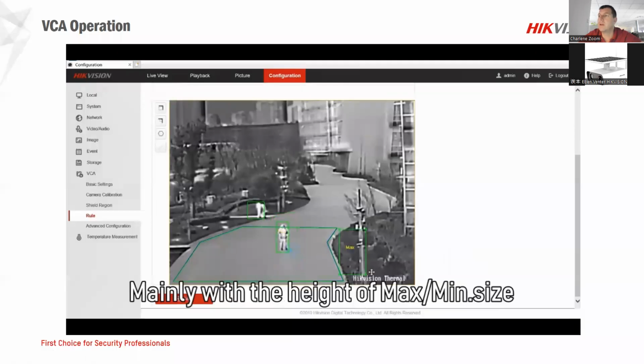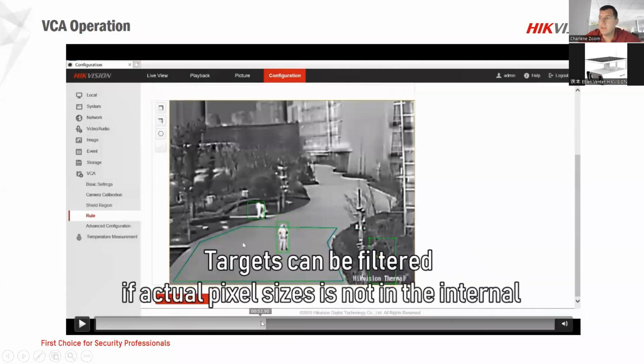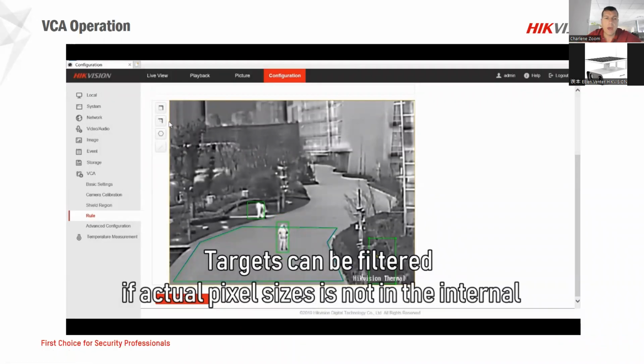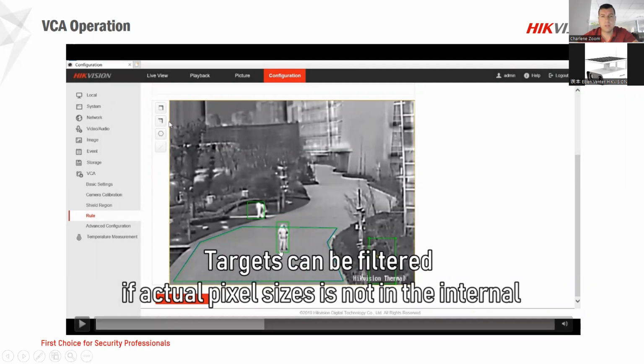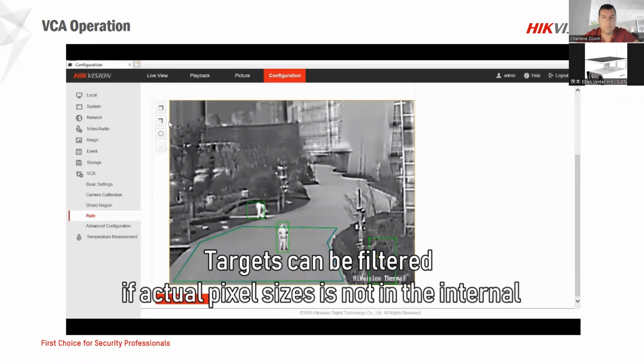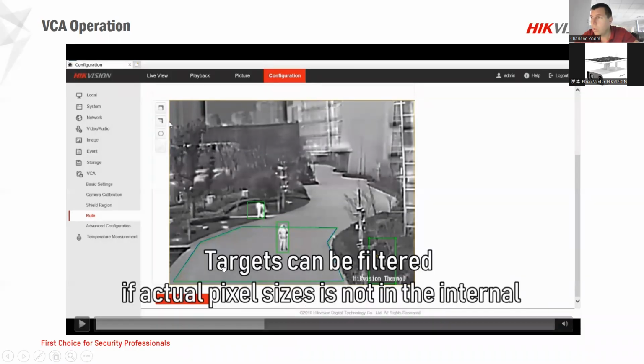So this tool is very nice. And that is another thing to mention. When it comes to this type of setup, with the majority of thermography type of things and any thermo cameras, the best is to do the calibration, and if you want to call it calibration, is to set it up. Right, you need to have that person straight in line of that view and close as possible. Put a person there, draw your minimum, draw your maximum. That is going to reduce your false alarms or your notifications quite a bit. This setup is a lot of homework, so it needs to be done correctly.